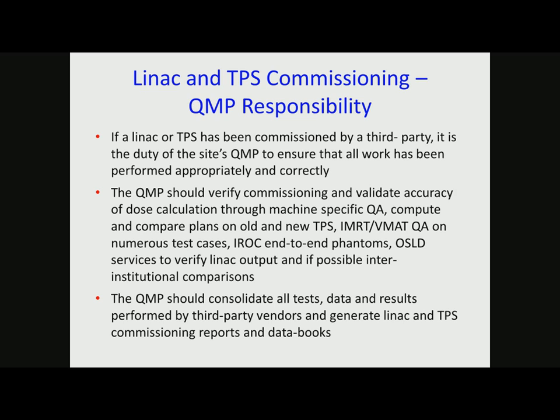In our clinic, we do annual OSLD checks on every Linac, which checks the output of each machine. You run a couple of treatment plans on it. If you commission a new treatment planning system, you run head and neck, prostate, and thoracic plans on the old treatment planning system, and then calculate them on the new one to see how close the two systems are to each other. You should have a bank of patient cases, maybe about 25 to 30 cases from different anatomical sites, complex and simple, and you can run IMRT QA and VMAT QA on these. It's a trend. Over the last 15 to 20 years, you can keep a track record of what your results should look like. So when you get a new Linac, you do the same thing over and over again.